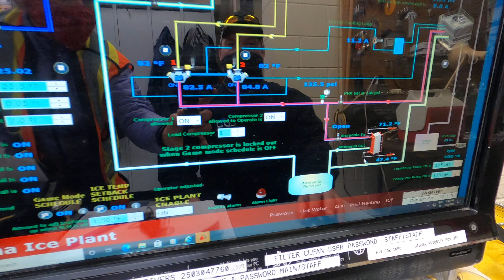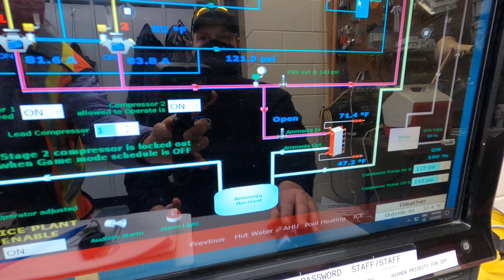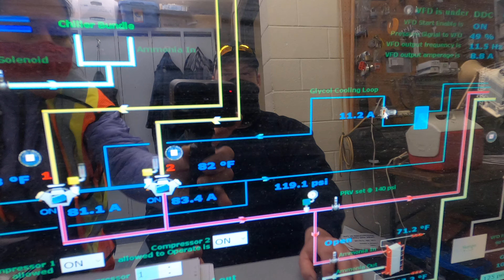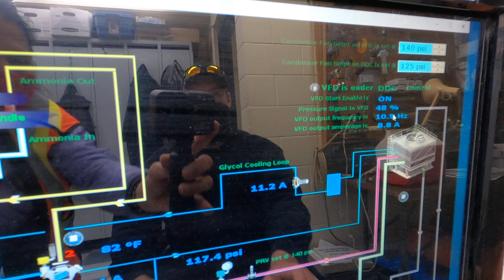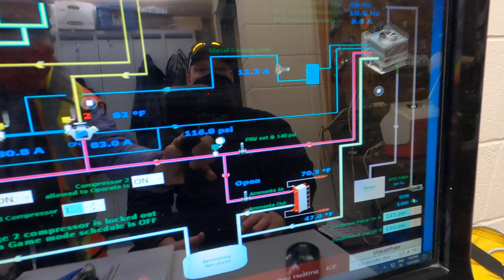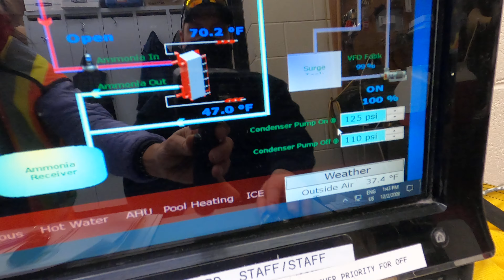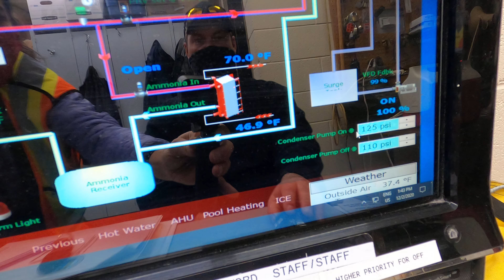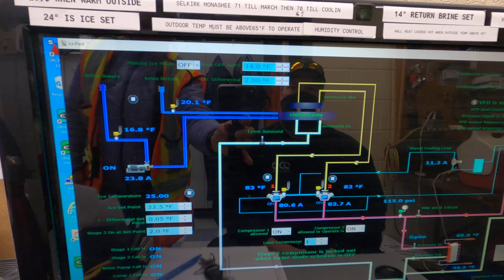Over here is just showing me my heat recovery, so ammonia in and out. So it's telling me what my temperature drops, or differentials, are between my glycols there. Up here shows me my glycol loop for my head cooling. So that pump is running. And then here is my evaporative condenser. Right now it's showing me that my VFD is spinning at roughly 48% of its capacity, and that my water pump down here is going at 100% capacity. And then it'll show you for the condenser pump, it won't turn this pump on below 110 psi and turns it on at 125. So it'll run that pump at 125 and higher. It will obviously turn off when it hits 110, and it never sees that until the plant is satisfied and it's actually turning off.